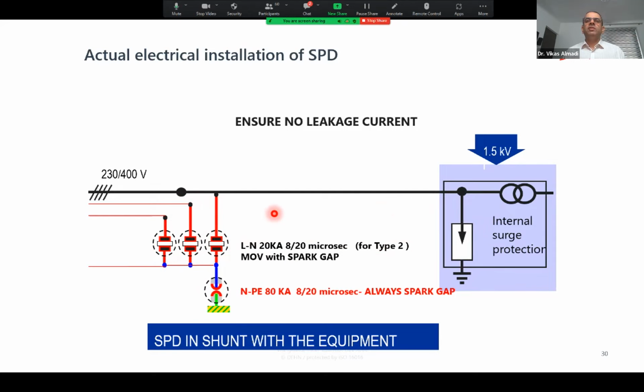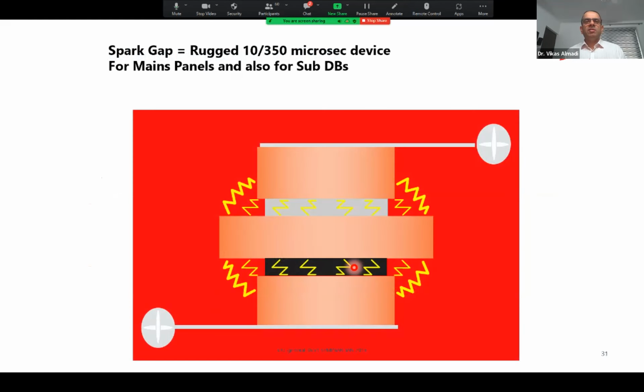And once this kind of arrangement is done, this should be able to protect the equipment, provided the voltage protection level is less than 1.5 kV and the energy that goes inside the equipment is less than 150 joules. So initially at the entry level, we will use the spark gap, which is going to create a kind of short, and of course this will take the maximum part of the lightning through this short, divert it, and whatever is left out, you have type 2 arrestors.